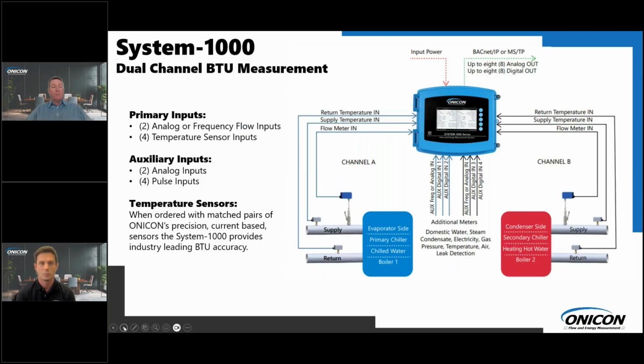You'll have 2 analog or frequency flow inputs, 4 temperature sensor inputs, 2 auxiliary analog inputs, and 4 pulse inputs for the System-1000. And when ordered with matched pairs of ONICON's precision current-based temperature sensors, the System-1000 provides industry-leading BTU accuracy. A couple other things I'd like to highlight here are that in the middle there, you can see you can pull in additional meters. Those can be domestic water, steam, condensate, electrical meters, gas, air pressure, any of those things. Also, you see there's only a single input power required for the System-1000. And then there's a single connection out to your building automation system. That includes up to 8 additional analog outs and 8 additional digital outs.